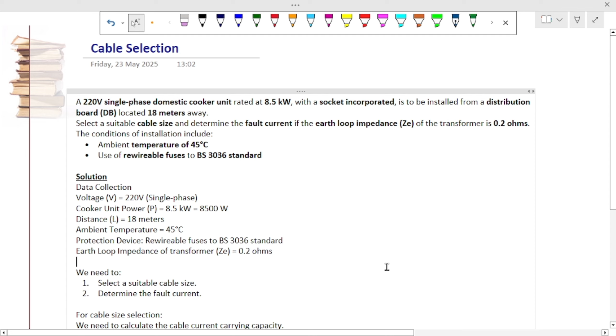Something I said some minutes ago is that in this course there are a lot of tables with data. Since this is what we have to do, let's focus on the cable size for now. For us to know what cable size to use, having this voltage and this power, we need to calculate the cable current carrying capacity. A 10 mm cable can carry a certain amount of current. 16 mm has its own current carrying capacity. So if we know the current carrying capacity, we can know the size of cable to use.